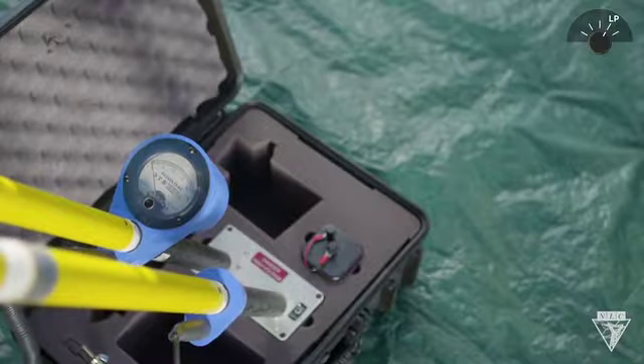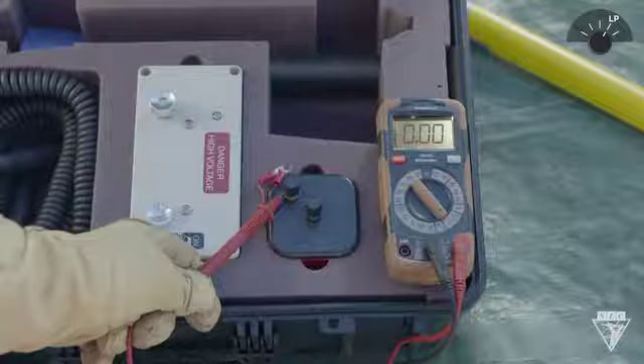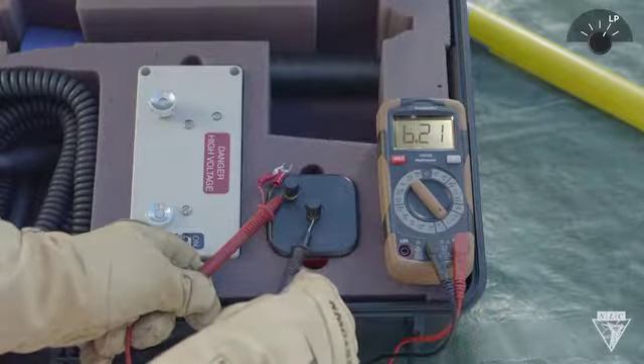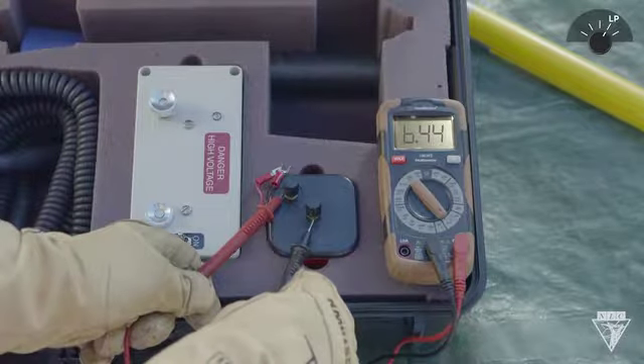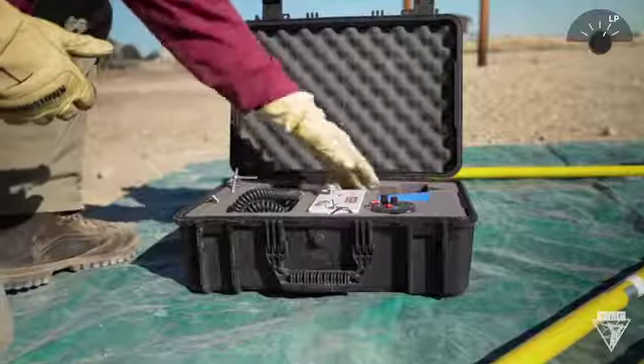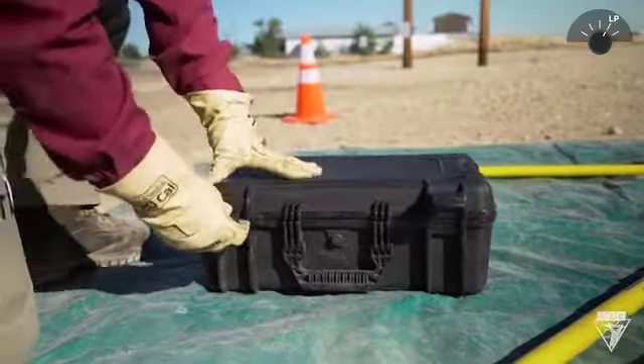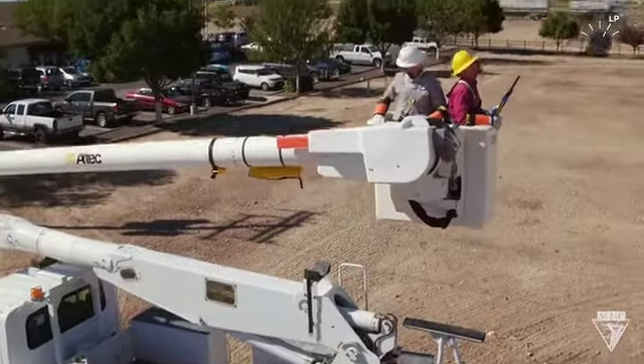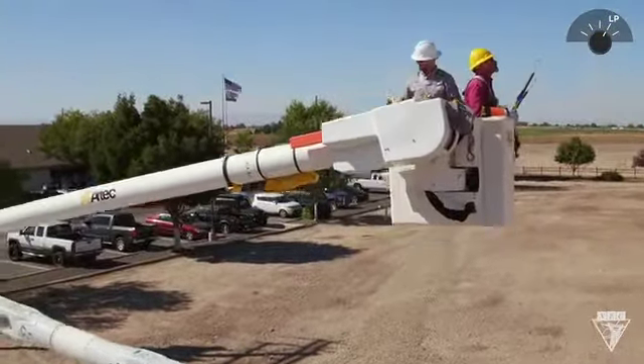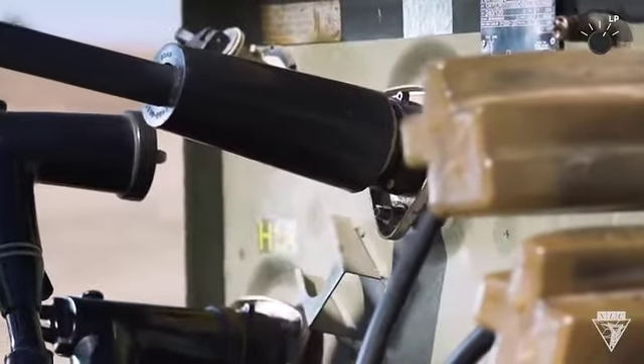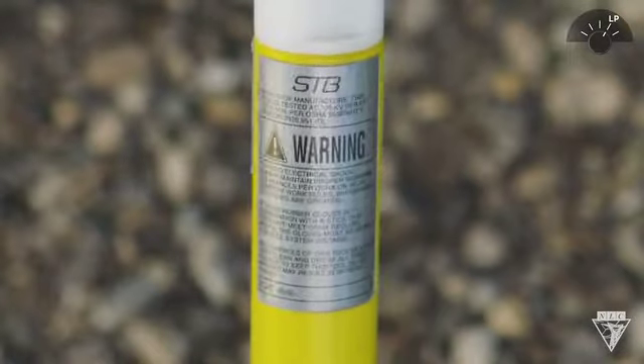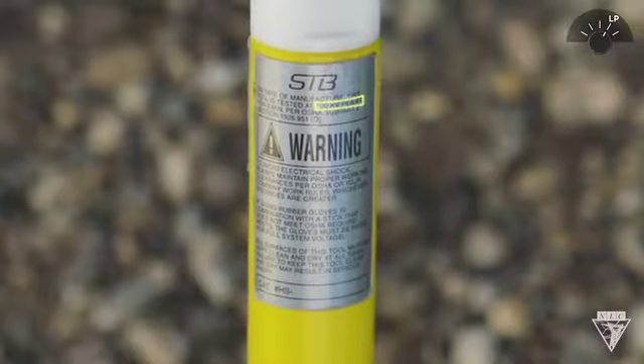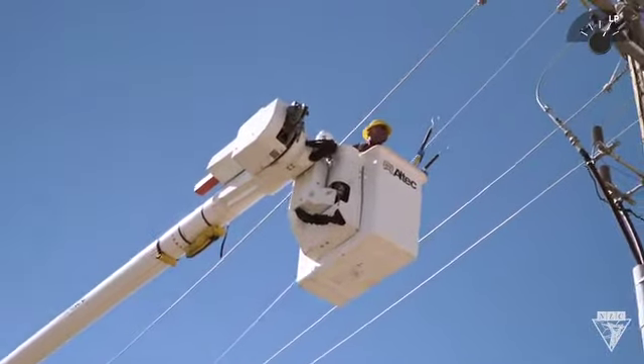If the red light does not turn on or the needle does not move, check the tester's battery. If the battery is good, the meter is defective and should be removed from service immediately. After testing, the meter can now be used to check phasing on overhead conductors or underground direct bushing contacts. Just be sure that your phasing meter and live line tools are rated for the voltage being tested.